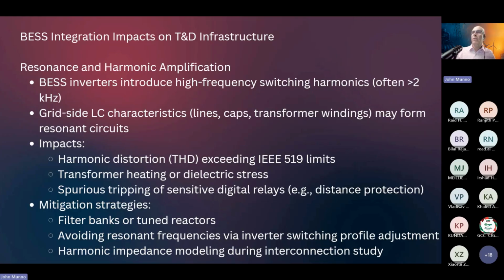So we have to be careful about measuring, monitoring, and protecting against the harmonics. And what we do there is we can use filter banks, tuned reactors. We want to avoid resonant frequencies with inverter switching profile adjustment and harmonic impedance modeling during the interconnection study. So we look at it before we install it. We don't want to try and fix it after the fact.